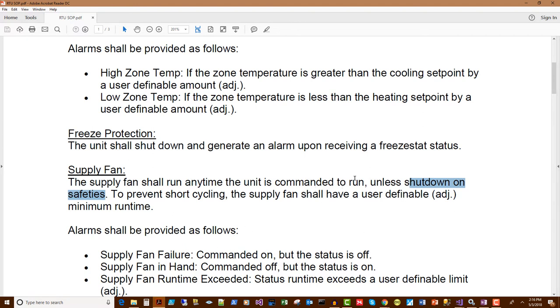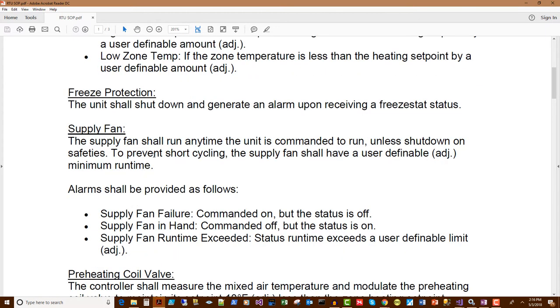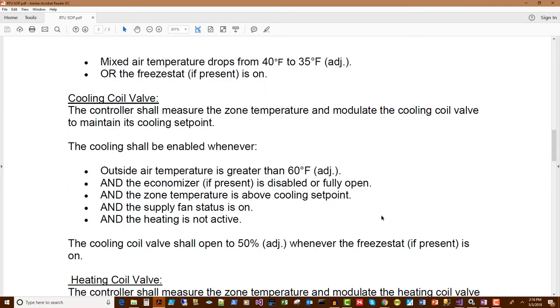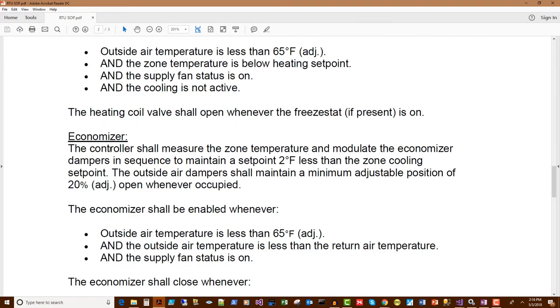Then what I'm going to do next is start to chunk out my programs. We have to ask ourselves, what on a rooftop do you think is probably the first thing we're going to do? We're going to turn on the unit, right? But what is the first thing? A lot of you are going to be tempted to say, turn on the supply fan. You are bad. Bad answer. No, it's open the economizer.